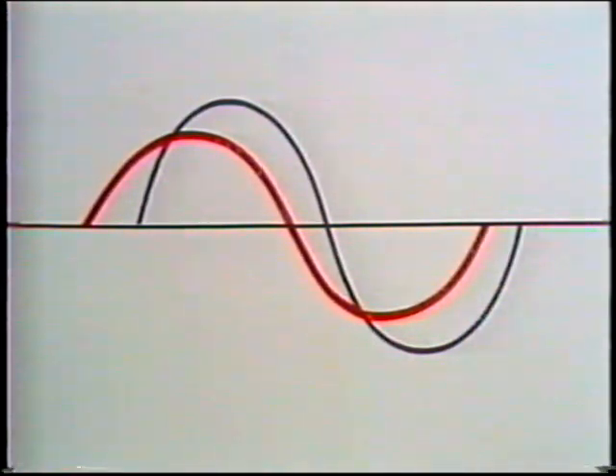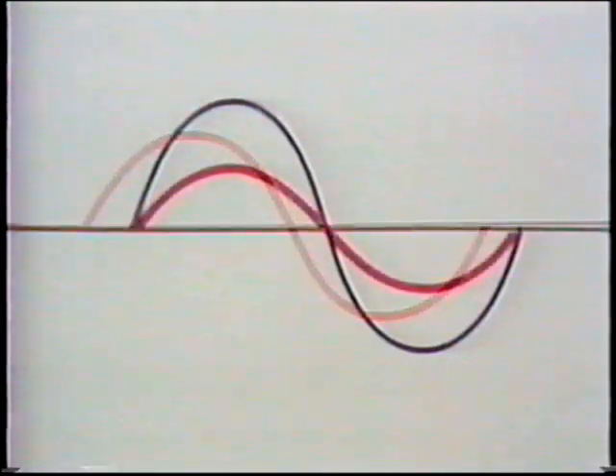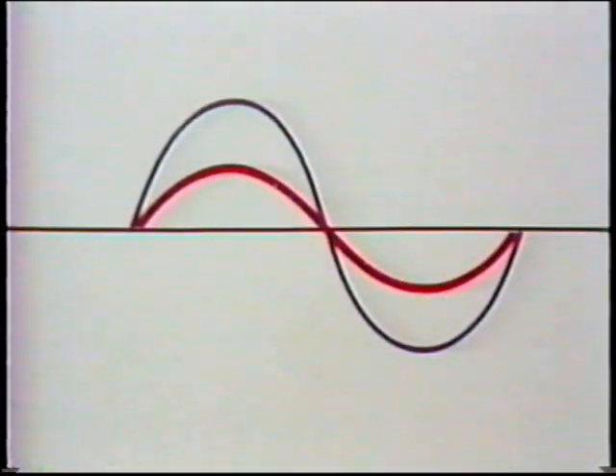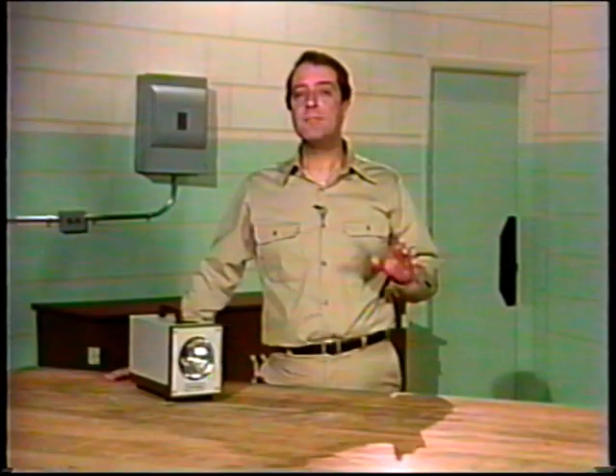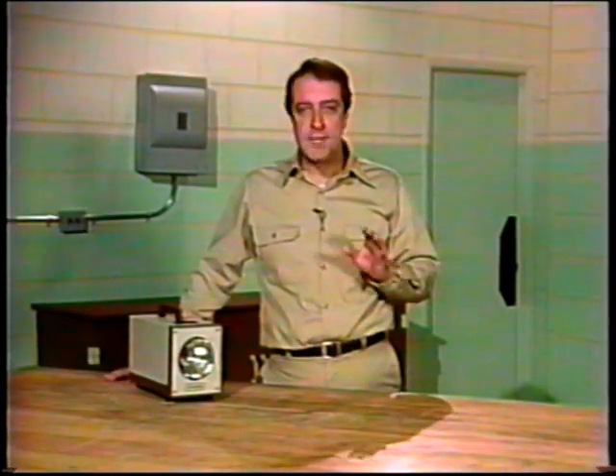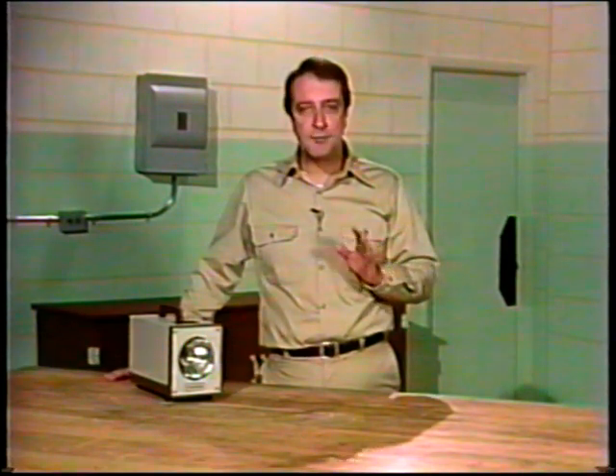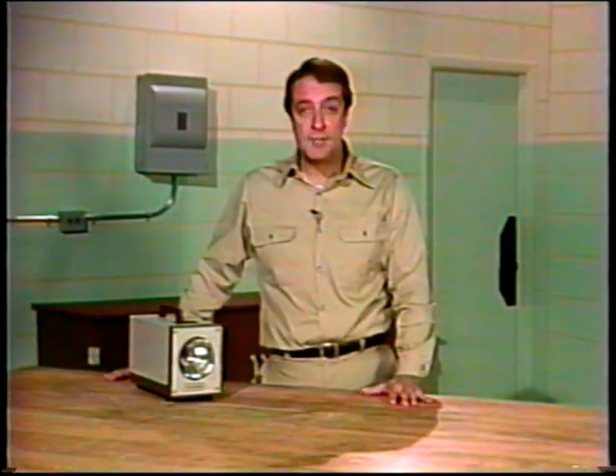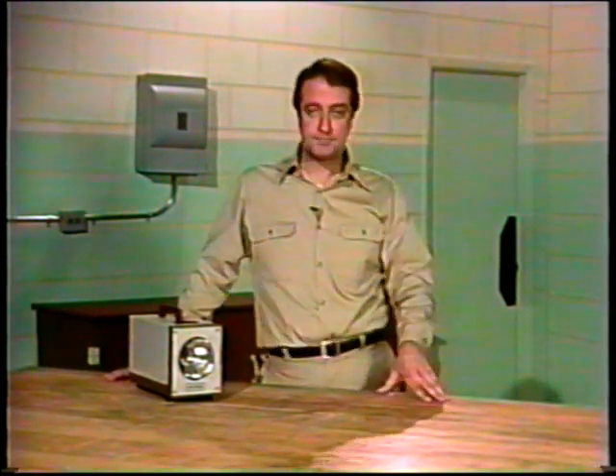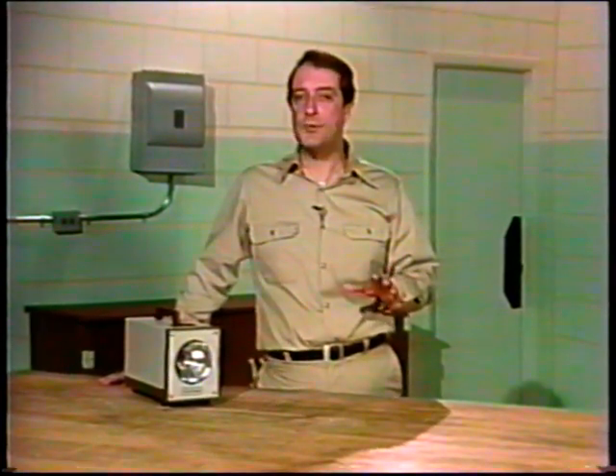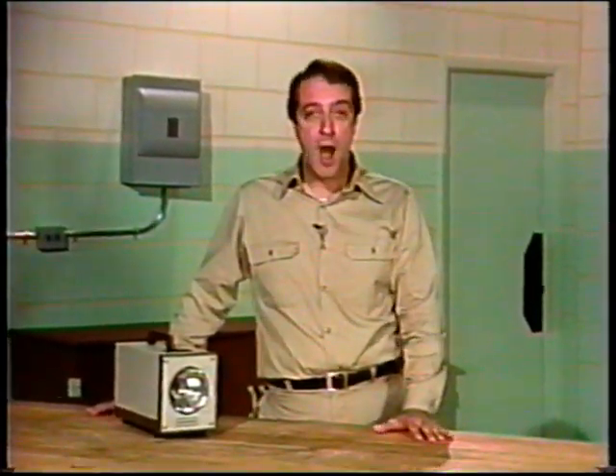That makes the synchronous motor less efficient, but it also causes the overall current to be more in phase with the overall voltage in the plant. Remember, the closer current and voltage are to being in phase with each other, the greater the electrical efficiency. So overexciting a synchronous motor can improve the overall electrical efficiency of an industrial operation. You may find that sometimes synchronous motors are used solely for this advantage. Power factor adjustment for improved electrical efficiency is an advantage characteristic only to synchronous motors. And this advantage makes a synchronous motor an asset to many industrial operations.